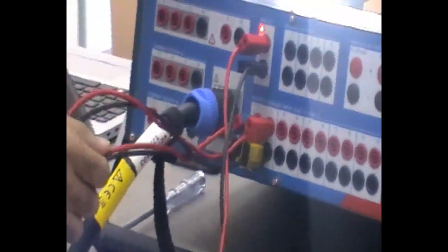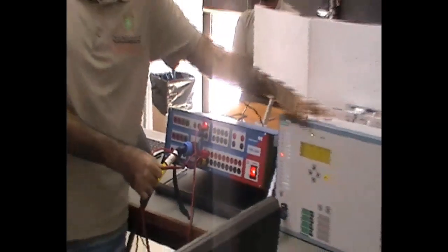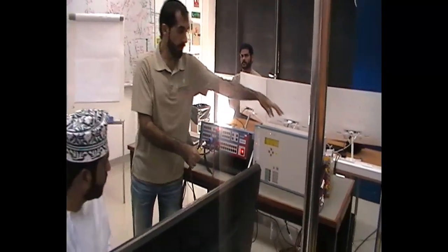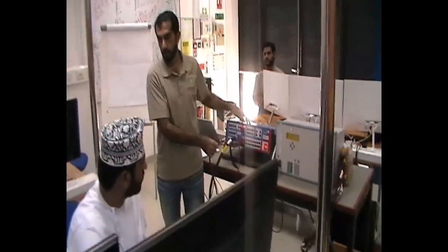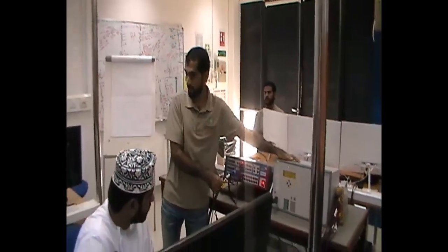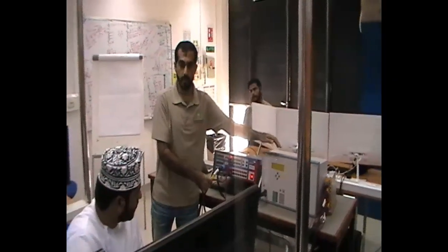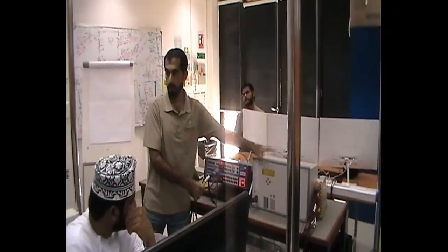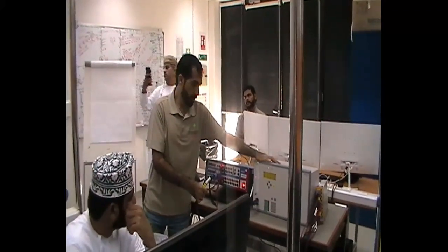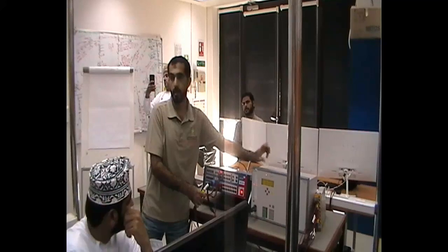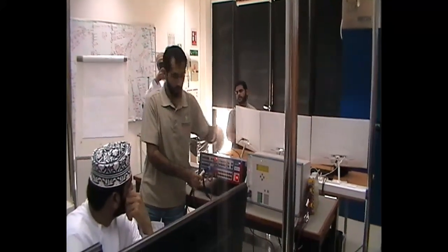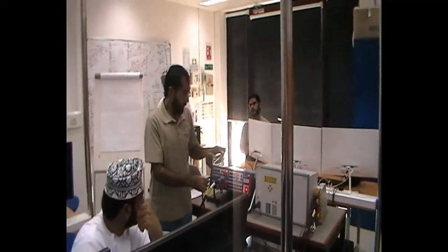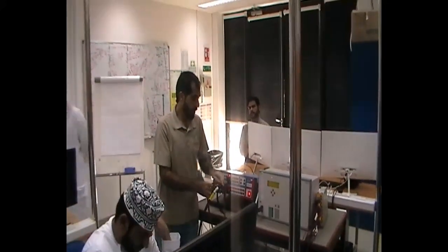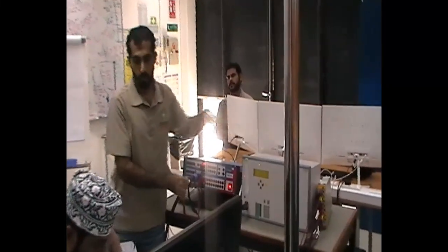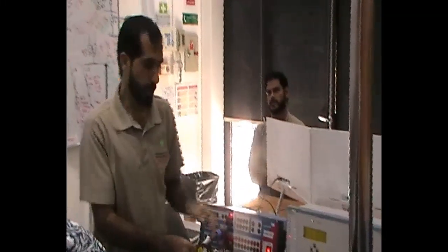Now, the second connection, I have a feedback. We have two types of it. There are more, but at least now we have two types. One is the trip signal: if the relay sends a trip signal, I'll receive it in the testing kit. In real life, it will go to the circuit breaker. The other is a pickup. Usually the pickup is when the relay starts counting, whether to work or not, but it takes time. So the pickup is usually used only to know whether the relay is working properly or not, or sensitive enough or not. So I have two types of feedback. In one type of test, I have to know which output is configured here as trip and which is start. I'll go through it again.